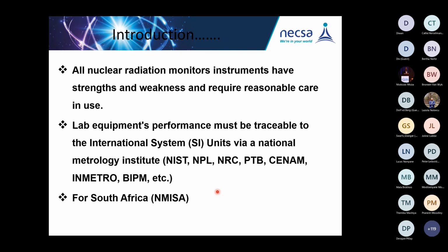That is the SI, via the National Metrology Institute. We've got NIST, NPL, NRC, the PTB, and also BIPM. Those are the primary laboratories, and NMISA sends their primary reference standard to any of these laboratories. Once NMISA has calibrated that, as South Africans, NMISA is the one that disseminates the chain of traceability to other calibration laboratories, any other laboratory whose reference standards are calibrated by NMISA. Therefore, they are already in the chain of traceability of measurements to the national measurement standard.